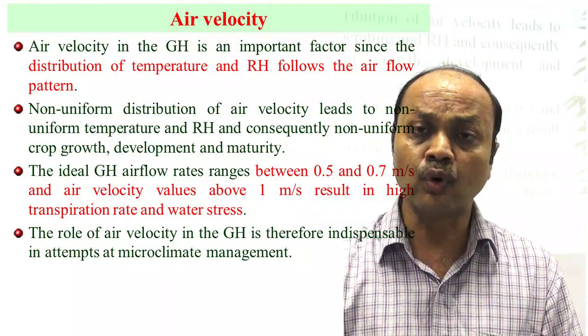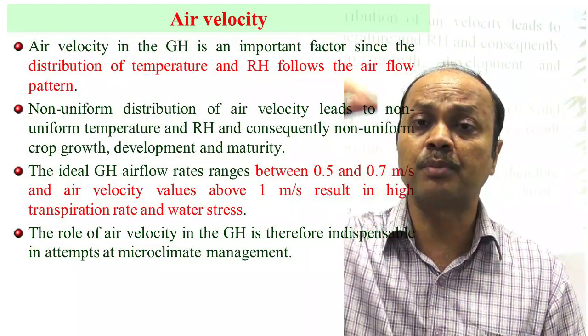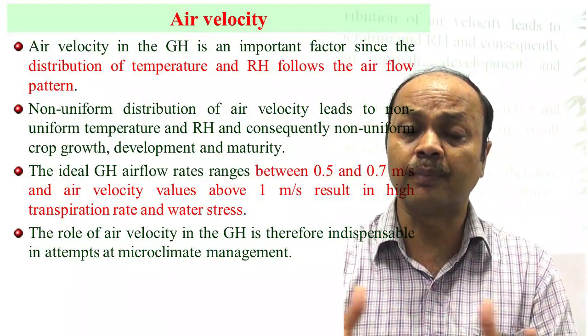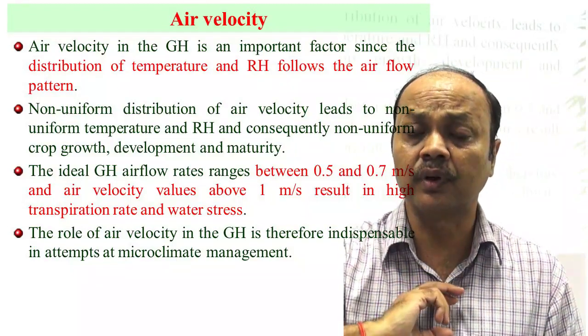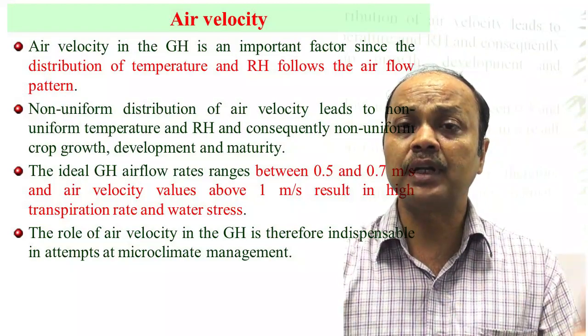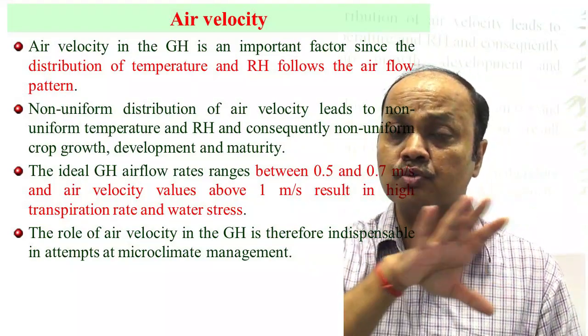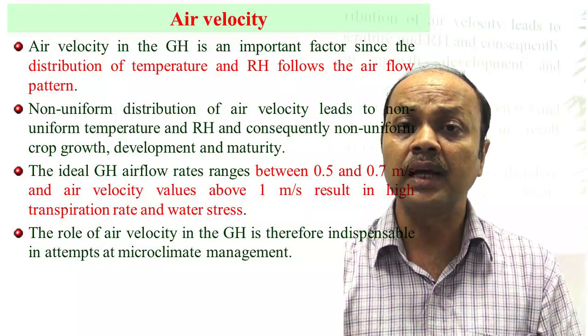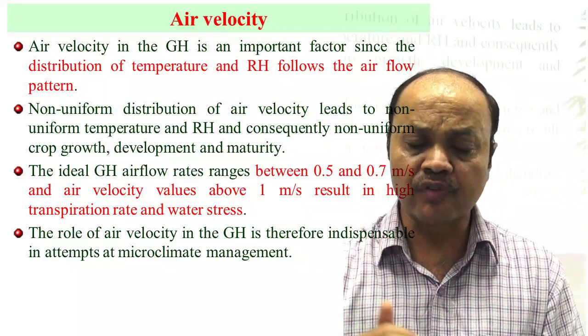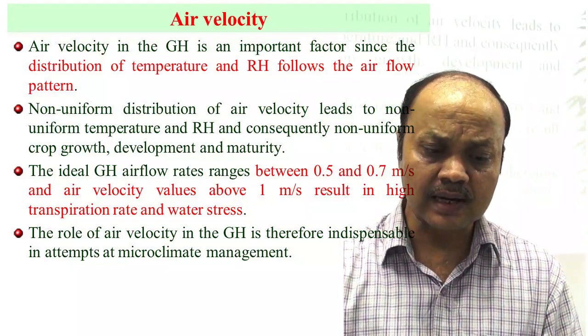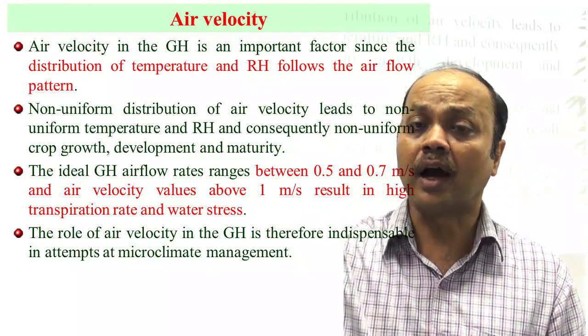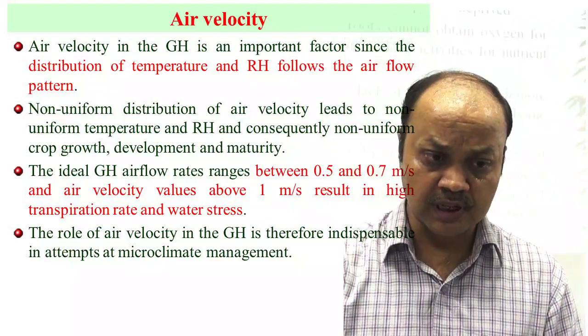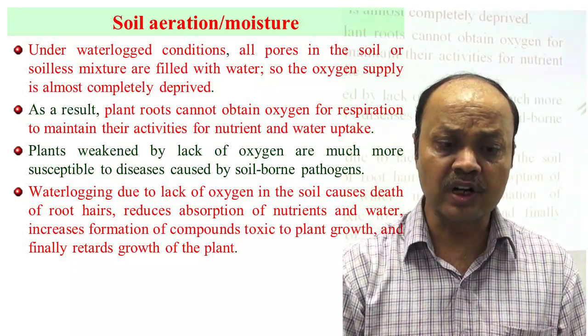If a plant is 10 feet tall, humidity at the lower portion may be higher and different at the upper portion. With adequate air velocity, temperature and humidity will mix uniformly throughout the greenhouse. The ideal air velocity in a greenhouse is between 0.5 to 0.7 meters per second. If air velocity is too high, fresh air replaces greenhouse air, increasing vapor pressure difference and thus transpiration.